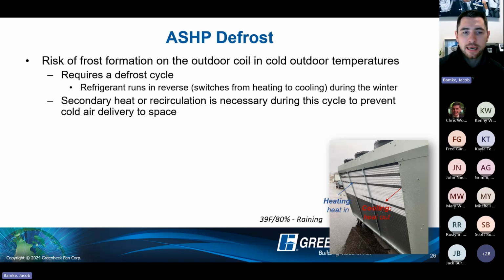In the testing that we did, we found that whatever was entering that indoor coil, if you were in a defrost cycle, you left that coil about 10 degrees cooler. So in this example, if I was entering at 39 degrees, I would be discharging about 29 degrees off that coil in defrost. That's where you need to size that secondary heat source.